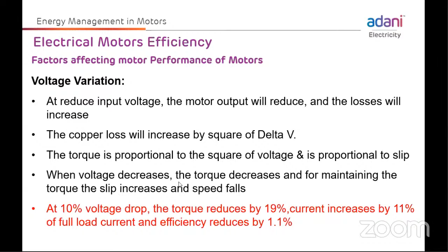Torque is proportional to the square of voltage and related to slip. When the voltage decreases, the torque decreases, and to maintain the torque, the slip increases and speed falls. At 10% voltage drop, the torque reduces by 19%, current increases by 11% of full load current, and efficiency reduces by 1.1%. This shows the effect of voltage variation on motor efficiency.